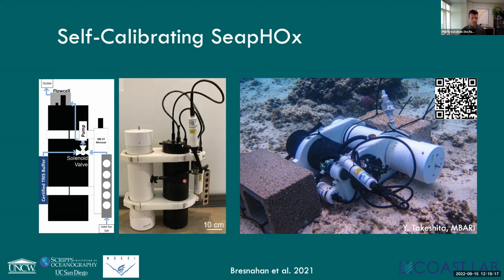The black housing on the right-hand side of this middle figure here, as well as all of the white parts that are connected to it on the right-hand side, that's a standard SeapHOx. And then in this PVC housing on the left-hand side, I realize the laser pointer is pretty glitchy here, so I apologize for that lagginess. The PVC housing on the left-hand side is storing our tris buffer reagent. And by periodically pumping the tris buffer through our system, instead of ambient seawater, we're able to get this autonomous calibration. Tris, I should mention, is extremely well characterized across a range of oceanic temperatures and pressures. And so as long as we have pretty good physical measurements, we know exactly what the pH of that tris is at any given time. And therefore, we're able to get a really good calibration on this instrument.